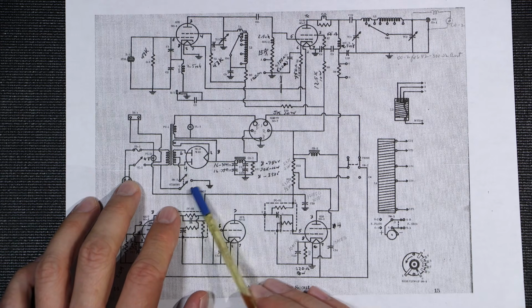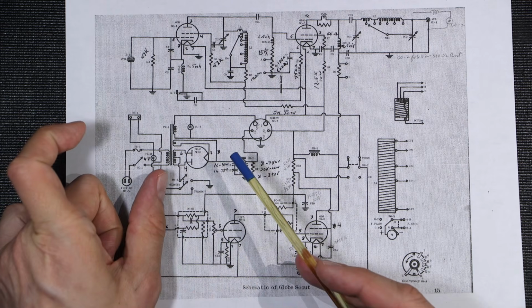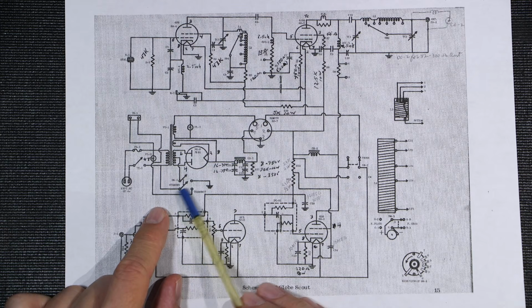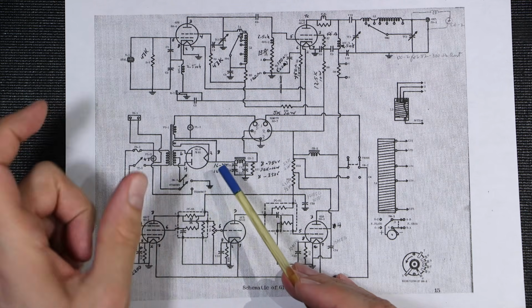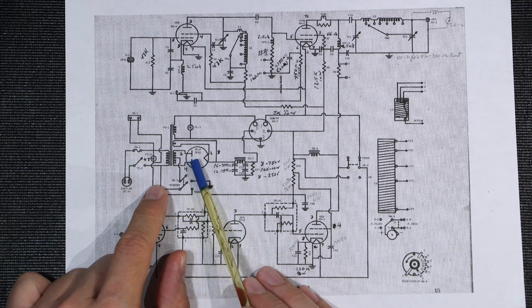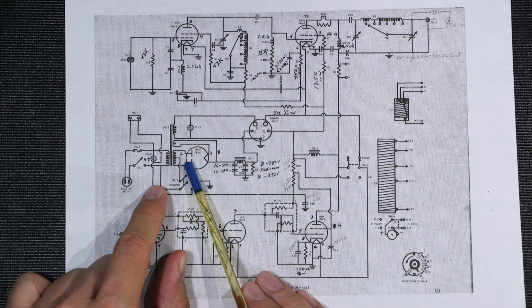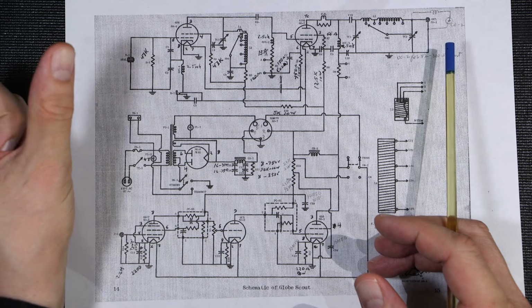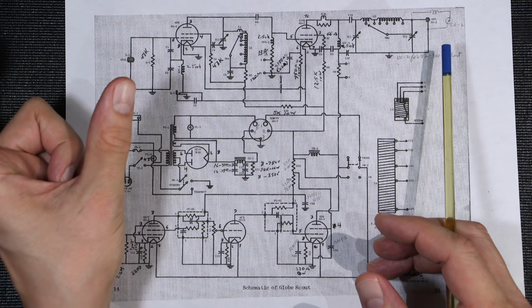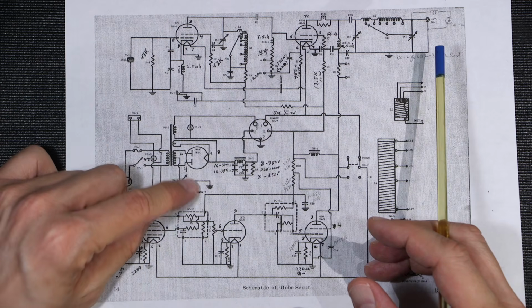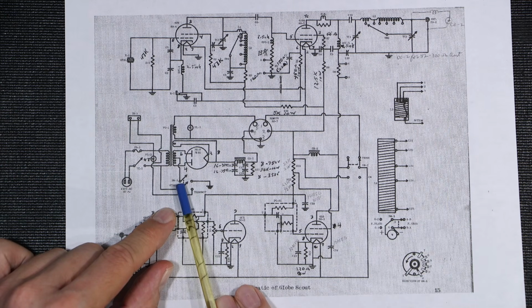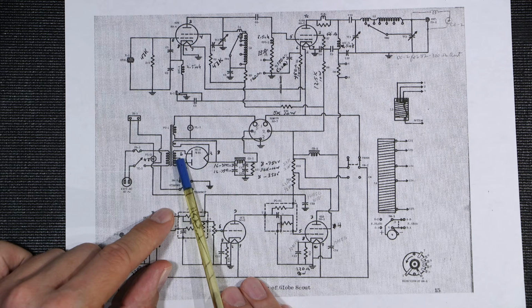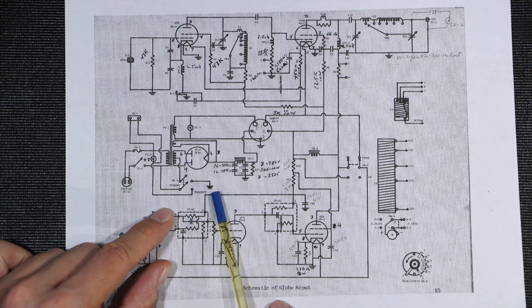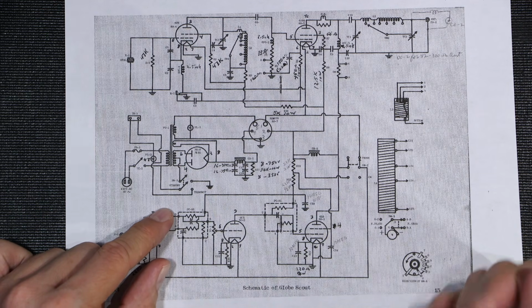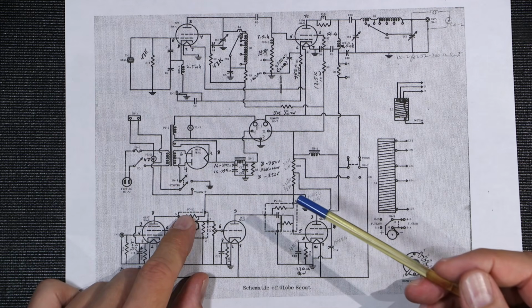So the standby and transmit switch is basically a double pole switch here. So single pole, or double pole, single throw, I should say. So you can see here the center tap of this transformer runs down to this switch here. And you can see that when you move the switch down to transmit, these two arrows are going to connect. So this arrow will connect here, this arrow will connect here. The center tap of the high voltage winding will be attached to ground. So that's what they're doing to cut the high voltage. They're just breaking the center tap.